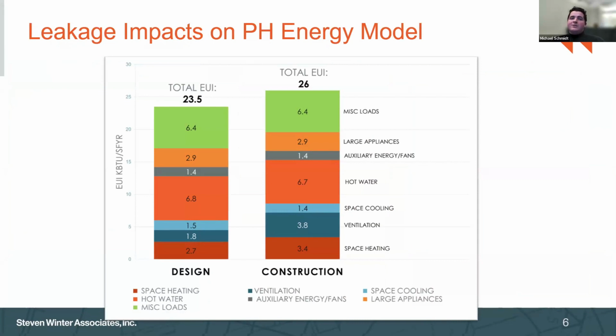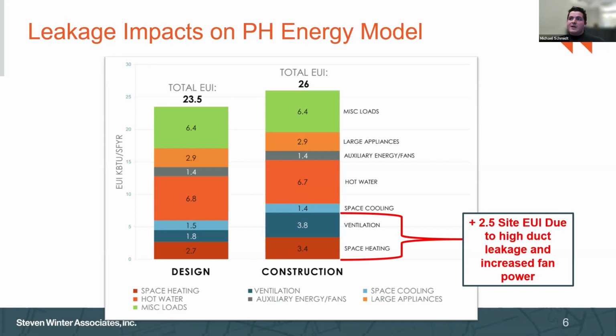So, duct leakage has an impact on our passive house modeling, particularly if we're accounting for things like fan wattage and higher flow rates based on the balancing. This is an example of a project that had very high levels of duct leakage, upwards of 40%. And this was when we had first done the review of balancing and inspections of the ductwork system. I think it's important to glean from this graphic that with high duct leakage and increased fan power, you can add a substantial amount of EUI to the total project's energy use. Here it was about 2.5. Now, obviously, they worked to remediate this as best possible.